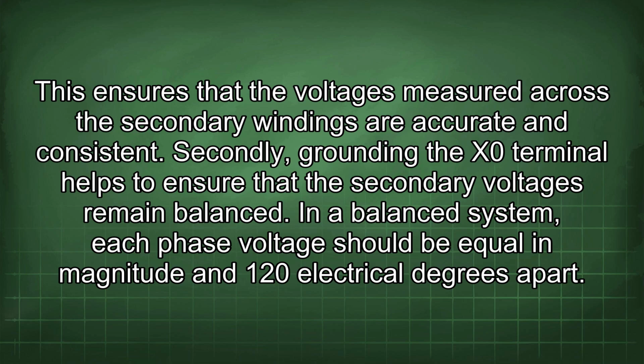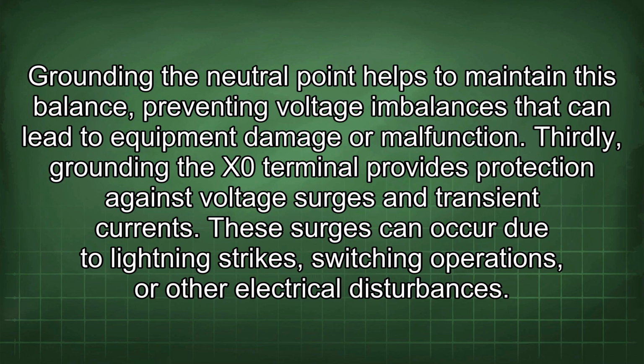Secondly, grounding the X0 terminal helps to ensure that the secondary voltages remain balanced. In a balanced system, each phase voltage should be equal in magnitude and 120 electrical degrees apart. Grounding the neutral point helps to maintain this balance, preventing voltage imbalances that can lead to equipment damage or malfunction.